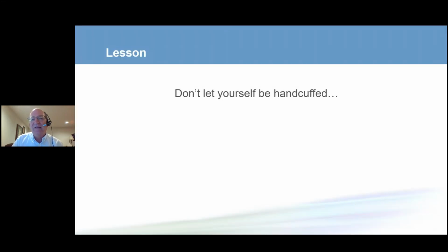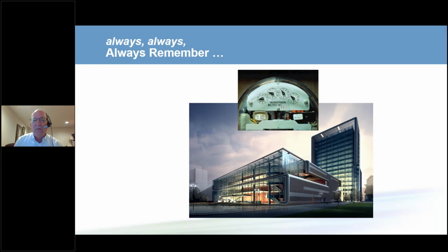So what I like to help people understand is that particularly in retrofit applications, you don't have to be confined or handcuffed by what the last designer or engineer did. You can use your knowledge and your experience to provide better value for the building owners. What we have to remember, though, is sometimes people will say, yes, but the chiller uses more power and it's the biggest motor in your system. And that's true, but that's not what the building owner pays for. The building owner pays for the entire system. And in that entire system, the energy use of that system goes down, and that's what the industry is telling us. So let's consider this for future applications, both new and retrofit.